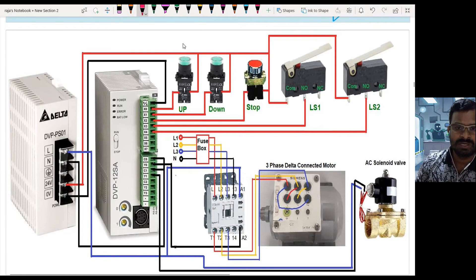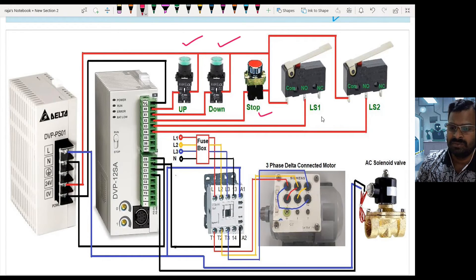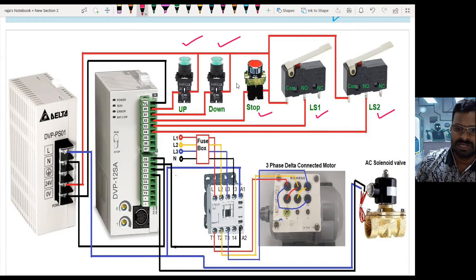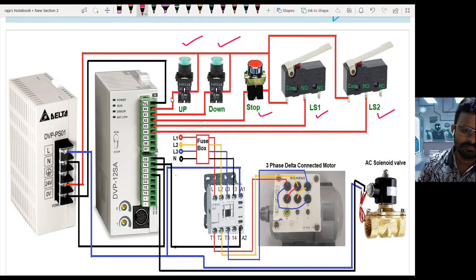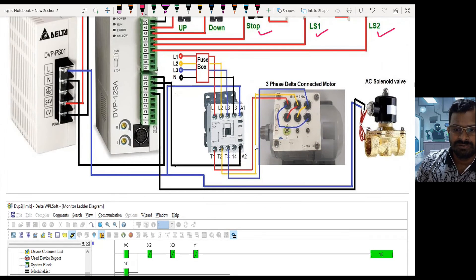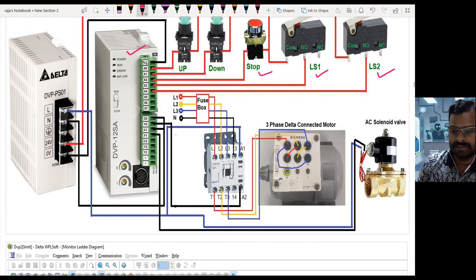Now let us see how it is connected to the PLC. I have two push buttons — one for up and one for down — plus one push button for stopping the process, with LS1 at the top position and LS2 at the bottom. These sensors are connected to PLC input module terminals X0, X1, X2, X3, and X4. The PLC module is in a sinking configuration, so the sensors act as sourcing elements. For output, I have one pump controlled through a contactor and one AC solenoid valve.